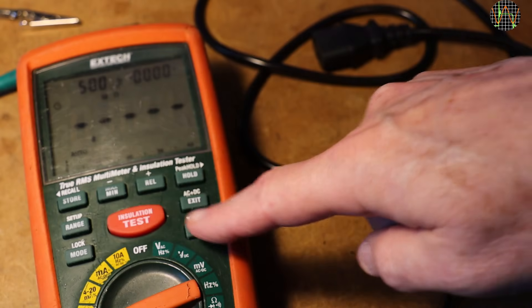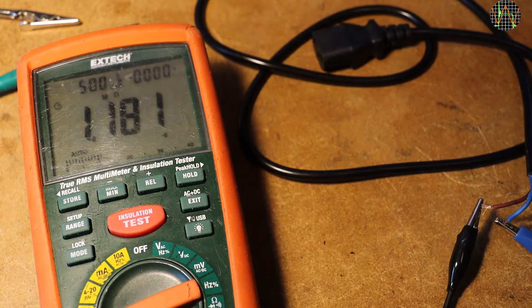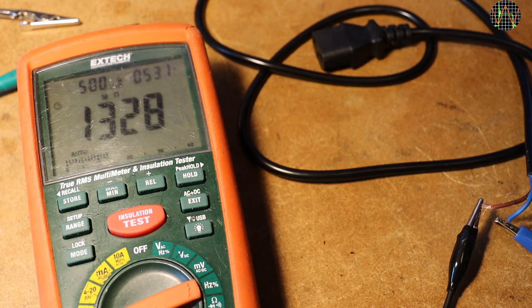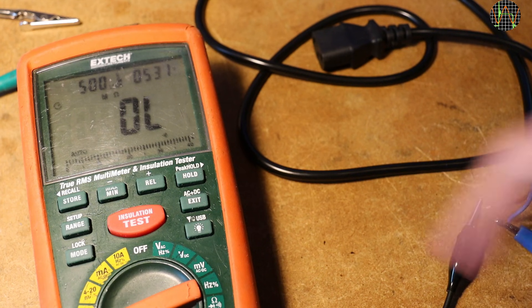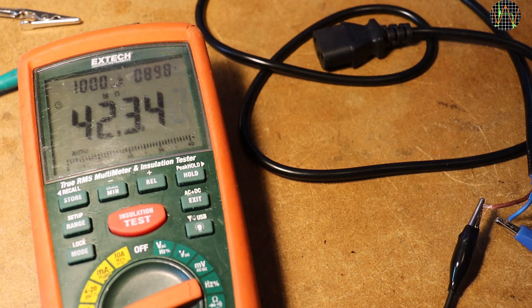I should have tested this before partially melting it, but anyway, let's see if the two wires could still handle high voltage. Starting with 500V. If you remember, the cable marking seemed to indicate that it was rated for 300-500V. There is no problem with 500V, which I find amazing given the state of the melted insulation.